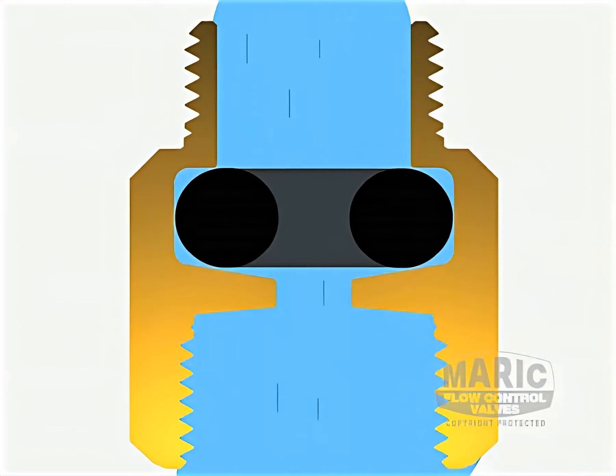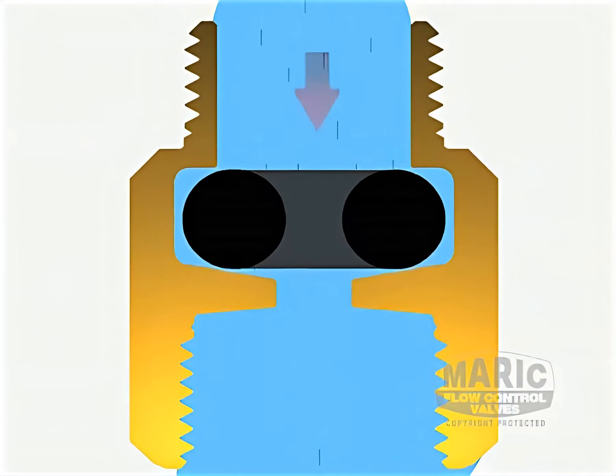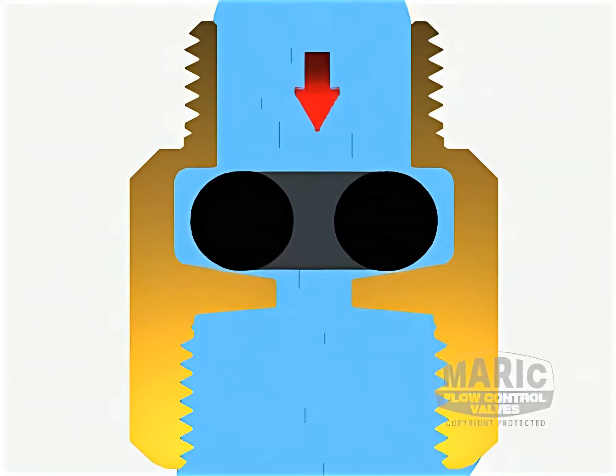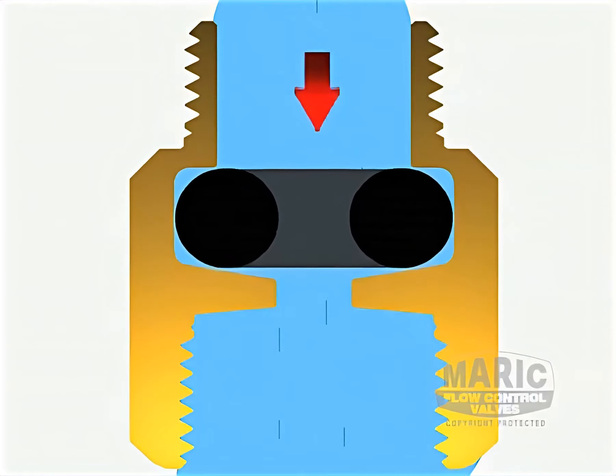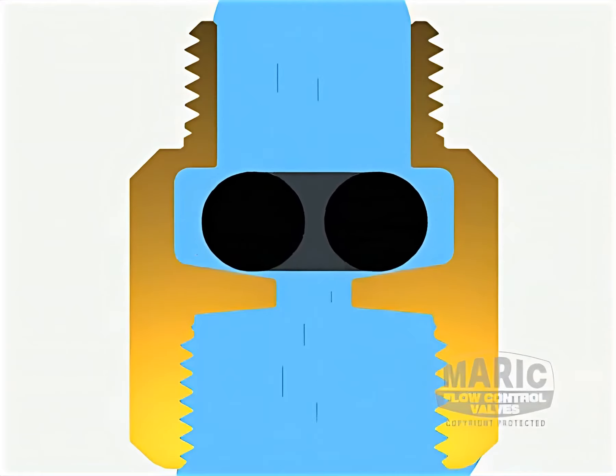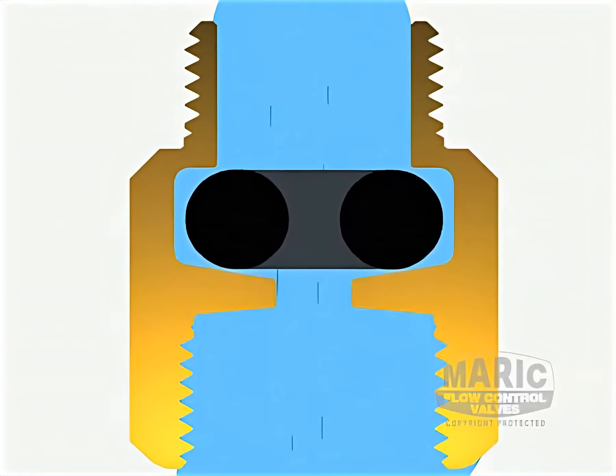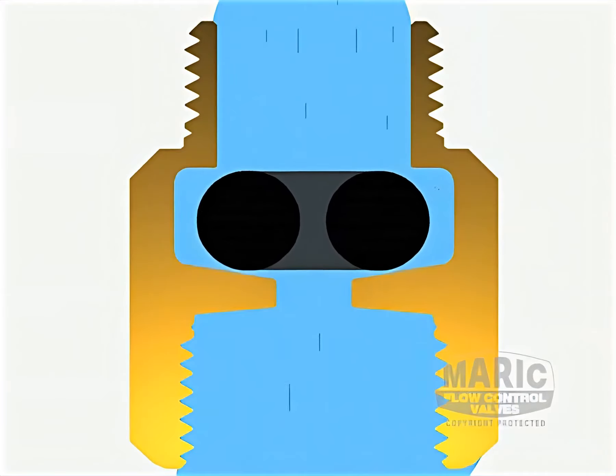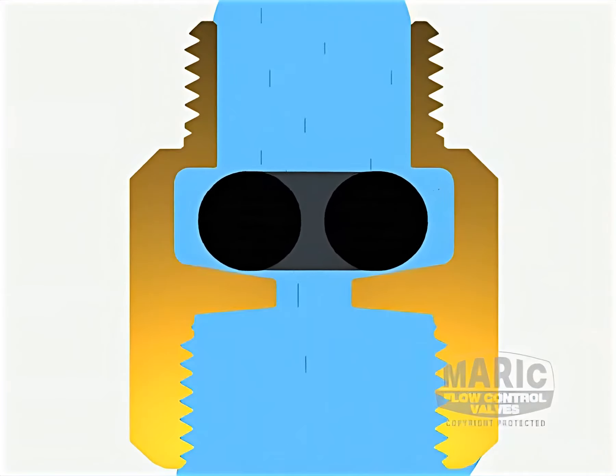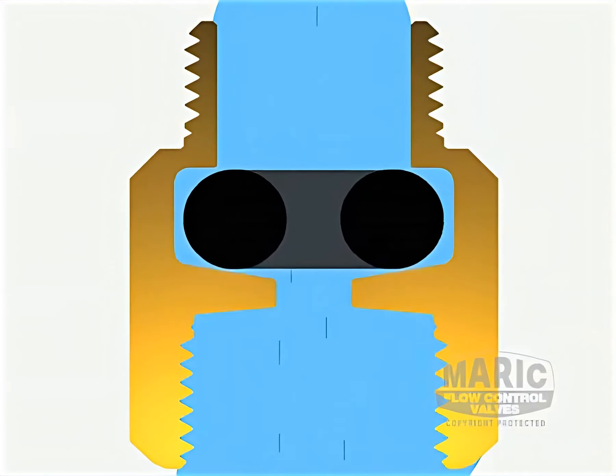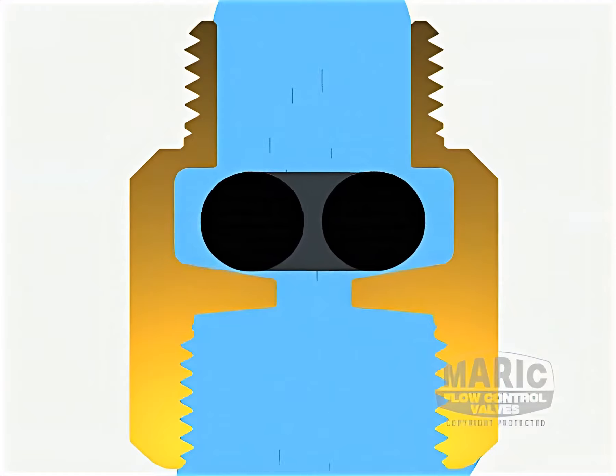The arrow indicates direction of water flow. The flexible control ring rolls down the tapered seat as water pressure increases, reducing the size of its own orifice, thus giving it a constant flow rate. The control ring rolls back up the tapered seat as pressure is reduced.